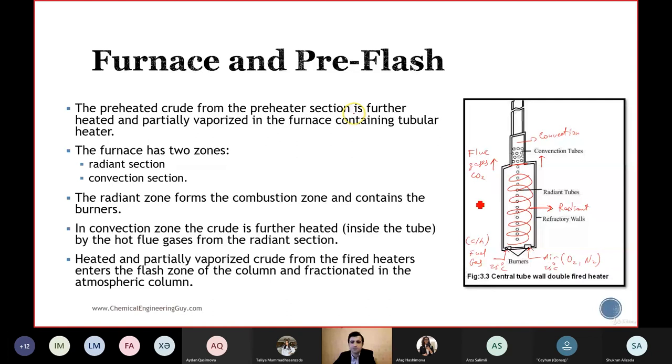These gases have a temperature of, I don't know, up to 200 degrees Celsius, even higher. And you have hot flue gases. Then you can add some more tubes here. In the convection section, you use the heat from the flue gases to heat your other streams. You can even produce steam here: you have a water inlet, and because of the high temperature, it leaves as steam. And then your flue gases leave the convection section at 120 Celsius.